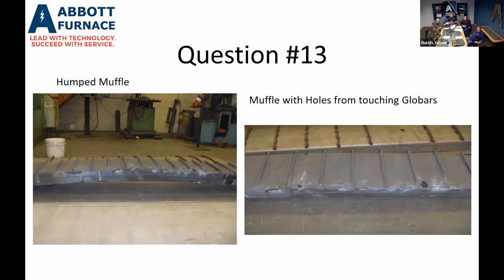We're going to ramp up again 100 an hour, and we're going to stop at 800 degrees for 2 hours. And we're going to come up to 1200 degrees. We're going to stop there for 2 hours. The important step in the process is the next one. We're going to come up to 1800, and we're going to stop there for 3-4 hours. And the reason being that stainless steel, 1800 degrees is kind of the sweet spot where as that muffle heats up, it's going to stretch, it's going to grow a little bit. And that's where we're going to see the most growth in that 1800 degree range, because those grains are growing. And once we get to 1800, we let that sit for a few hours, those grains are going to grow to their kind of maximum size. So after that, the grain size is kind of set in stone.